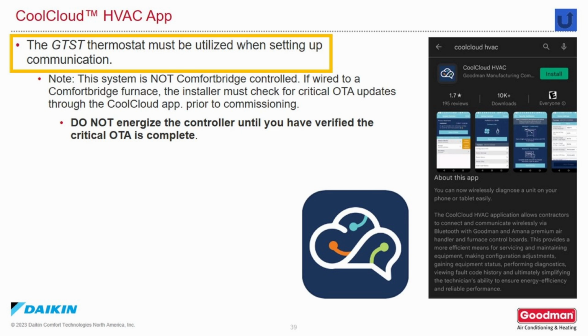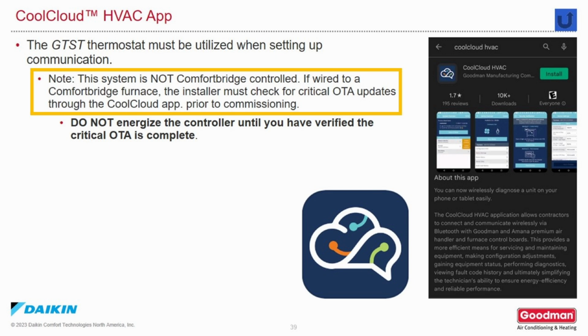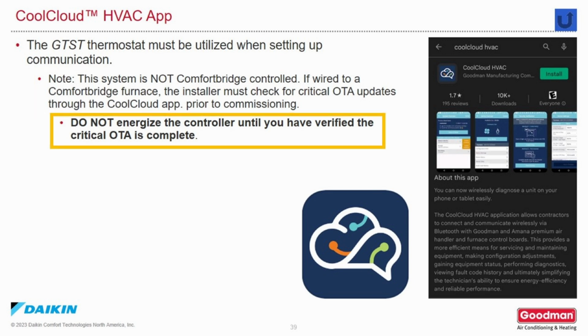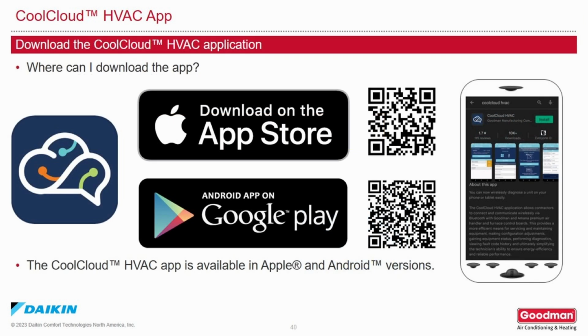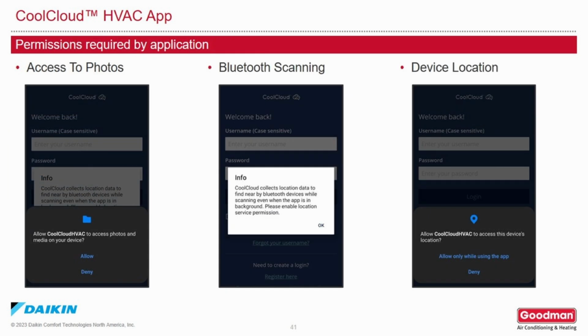The GTST thermostat must be used when you're setting up communications in this system. Note that the system is not ComfortBridge controlled. If it's wired to a ComfortBridge furnace, the installer must check for critical OTA updates through the CoolCloud app before commissioning the system. Do not energize the controller until you have verified that the critical OTA update is complete. The CoolCloud app is available in Apple or Android versions and can be found in the Apple Store or the Google Play Store. When setting up the CoolCloud app, there are 3 permissions required by this application: access to photos, Bluetooth scanning, and device location.